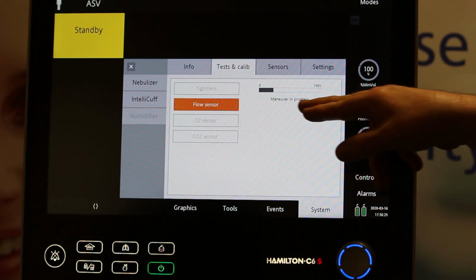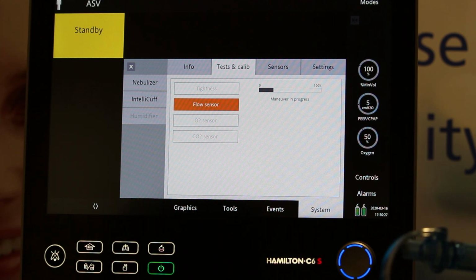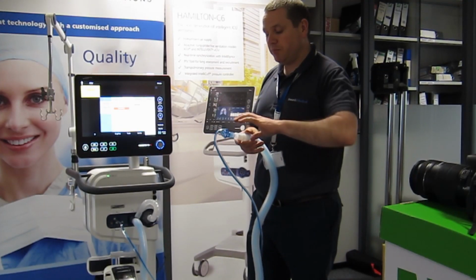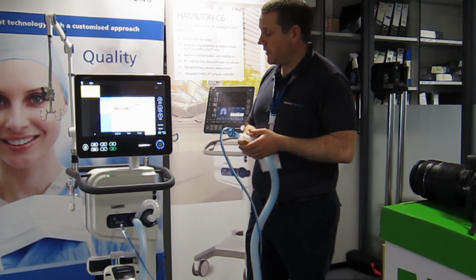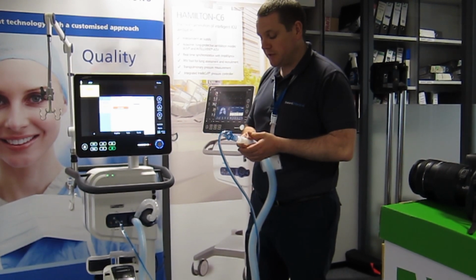Now you see it says manoeuvre in progress. So what the vent is going to do now is blow air at 4 different rates over the sensor. It knows what rate it's blowing at, so it knows what the sensor should read. And then halfway through it's going to prompt me to turn the flow sensor back around to do the same manoeuvre in the opposite direction.